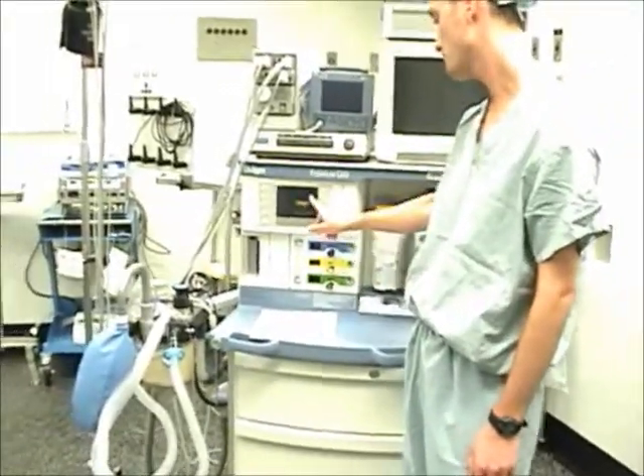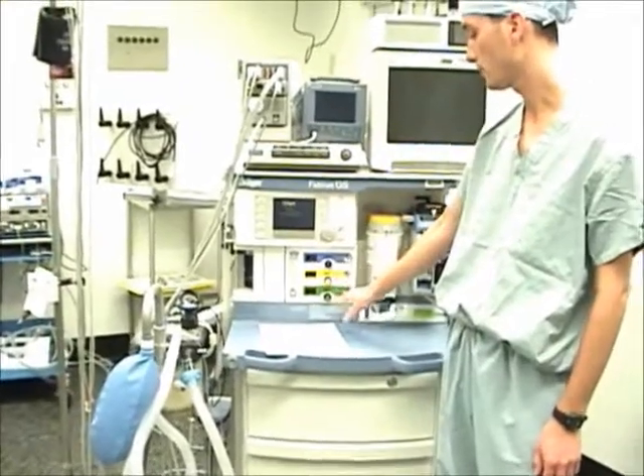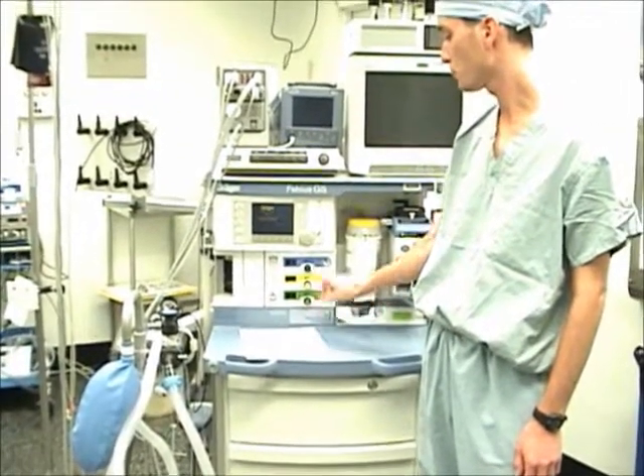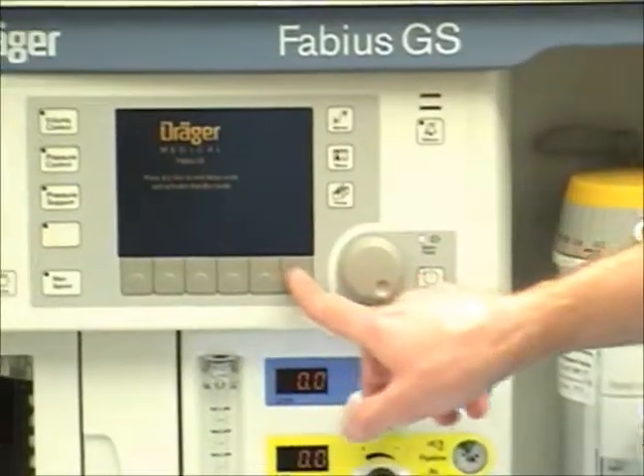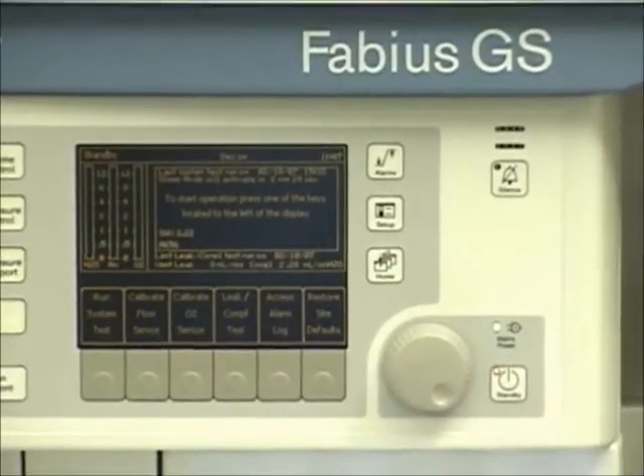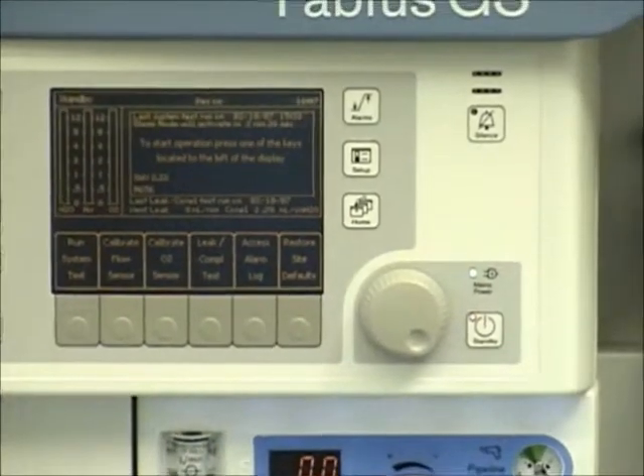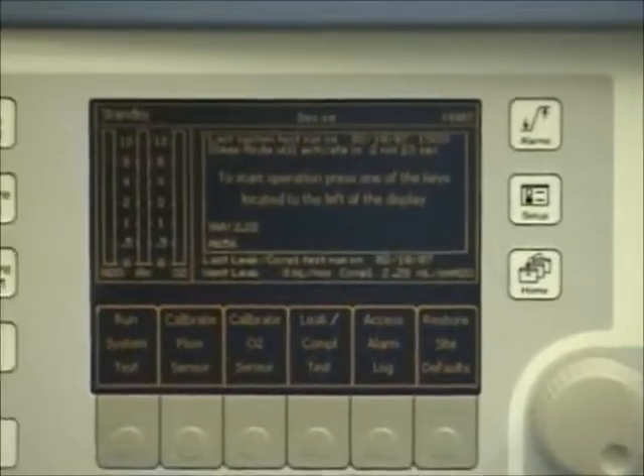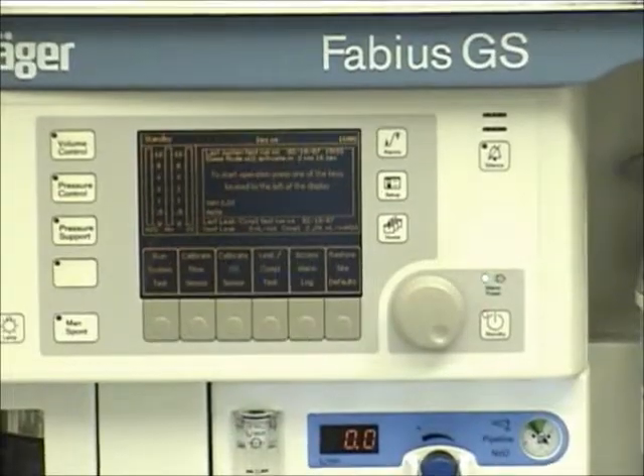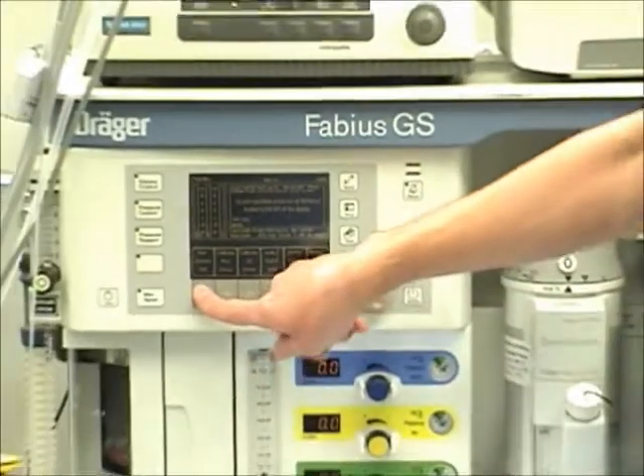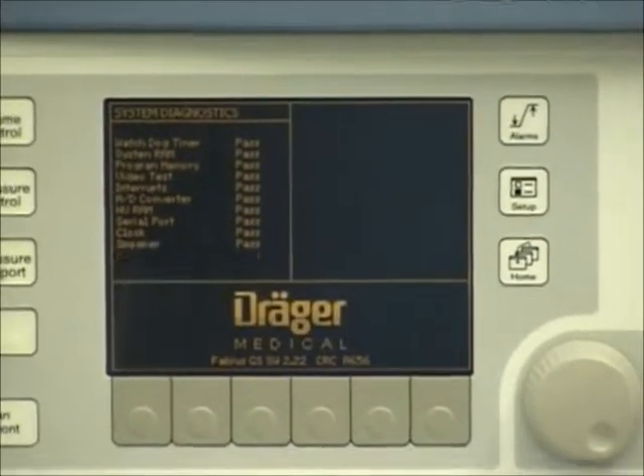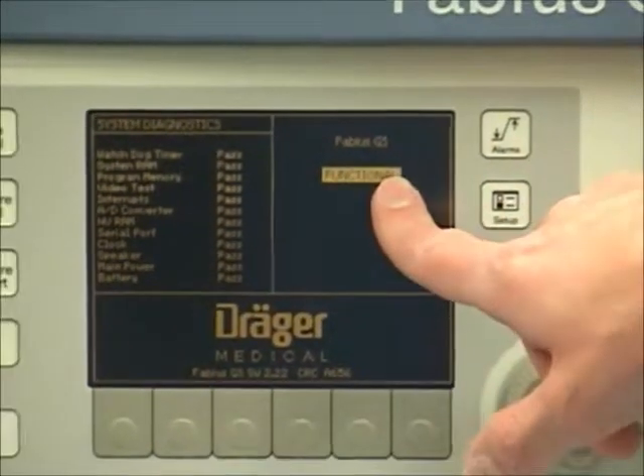The Fabius GS machine is not equipped with an on-off switch, but rather reverts to a sleep mode following several minutes of inactivity with no gas flow. To awaken the machine from sleep mode, press the rotary dial or any soft key on the interface panel. The machine is now in standby mode. To run a system test, press the corresponding soft key on the interface panel. The display indicates that the machine is functional.